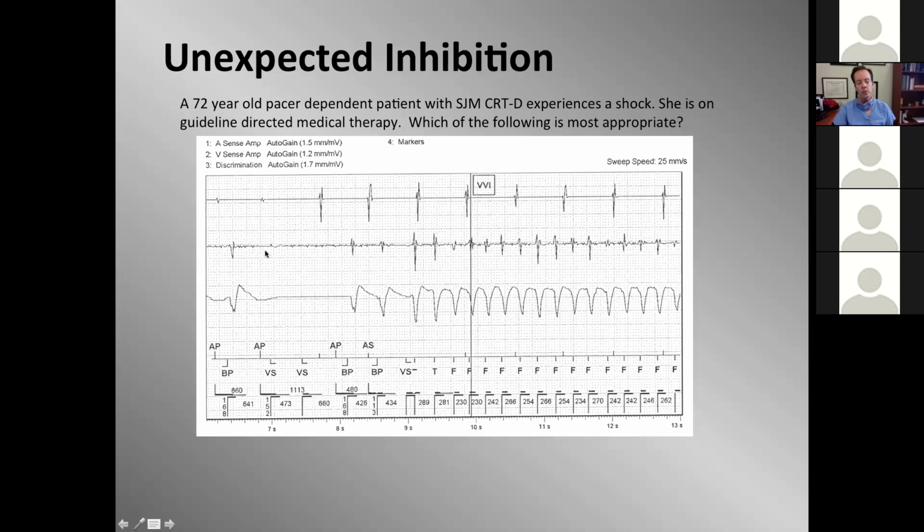However, there are numerous cases of the low frequency attenuation filter augmenting high frequency signals. And so you can see phrenic myopotentials or other high frequency nothings that don't represent lead malfunction, but are solely attributable to the filter itself. And in this case, it resulted in asystole, long short, and true VF that luckily was sensed and treated.